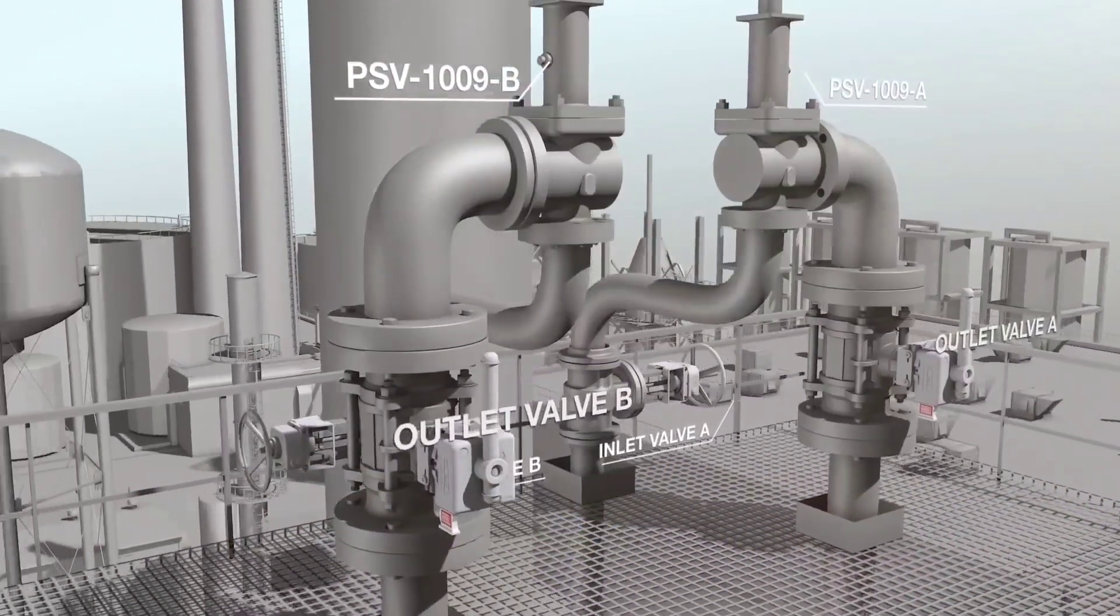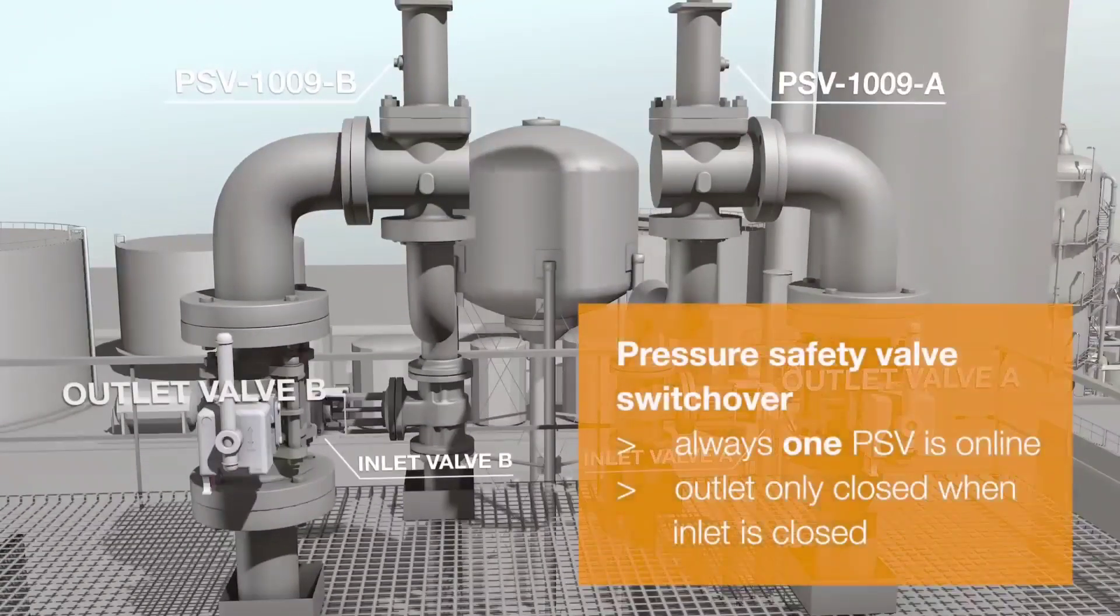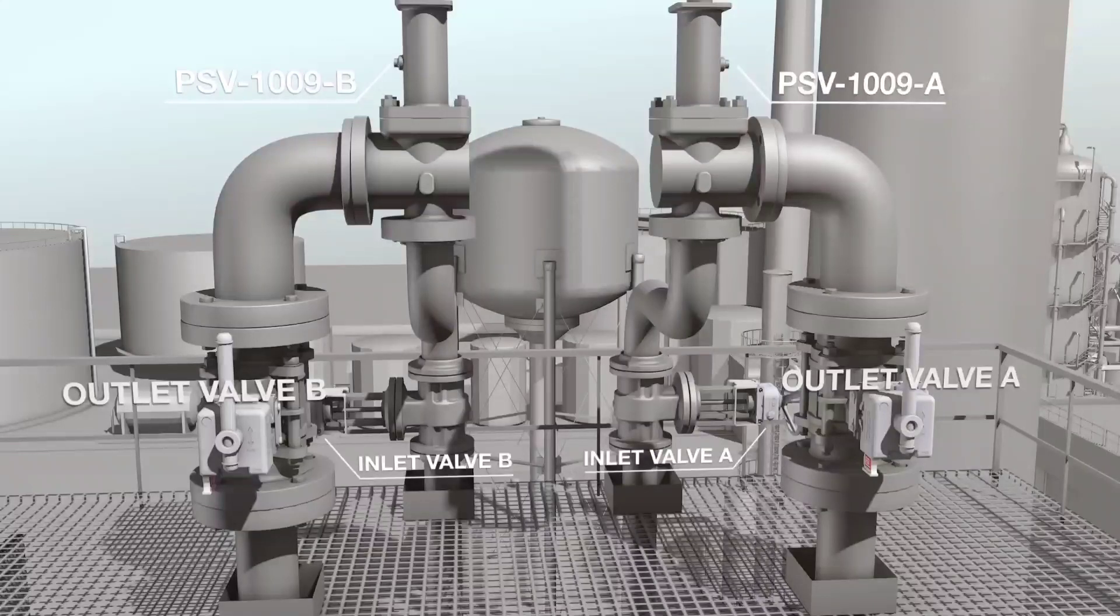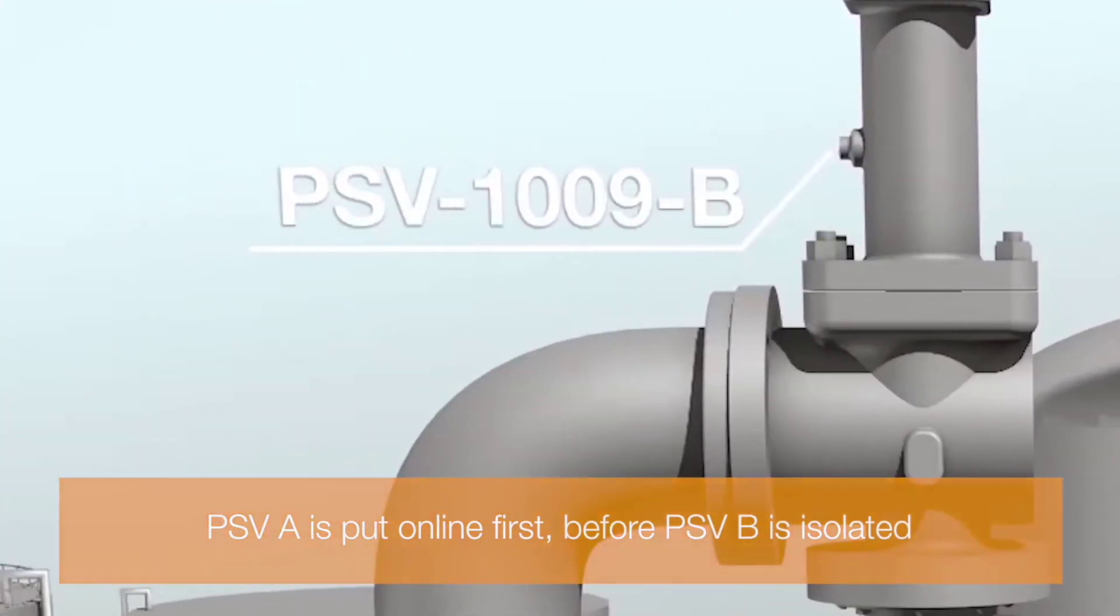In a parallel PSV system, inlet and outlet valves are interlocked to ensure that at least one relief valve is online at all times. In this example, PSV-A is put online first, before PSV-B is isolated.